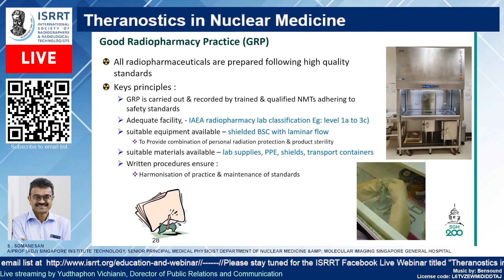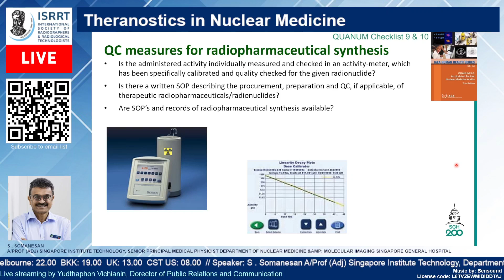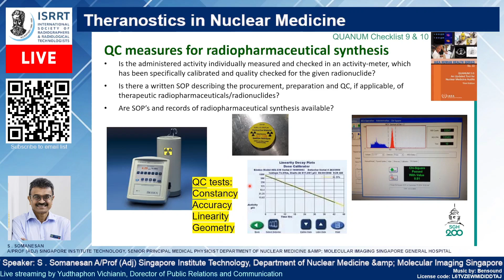For example, in every type of radiopharmaceutical compounding or synthesis, and also drawing out doses aseptically. For QC measures of a radiopharmaceutical synthesis, is the administered activity individually measured and checked in an activity meter, which has been specifically calibrated and checked routinely for the given radionuclide? Is linearity done? At the same time, is constancy done for these dose calibrators with the various radionuclides? Is there a written SOP describing the procurement, preparation, and quality control, if applicable, of the therapeutic radiopharmaceutical or radionuclide that is utilized? Are SOPs and records of radiopharmaceutical synthesis available in the department? Are QC tests such as constancy, accuracy, linearity, and geometry done at regular intervals as well?